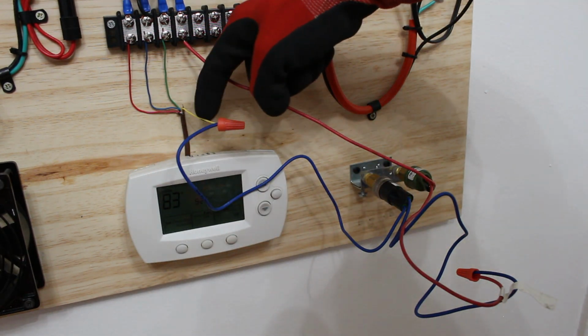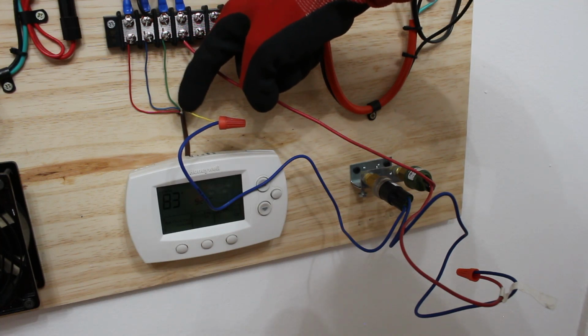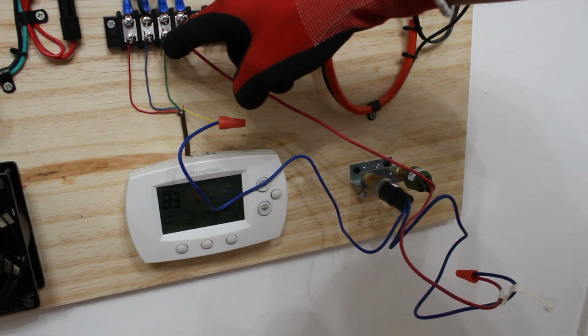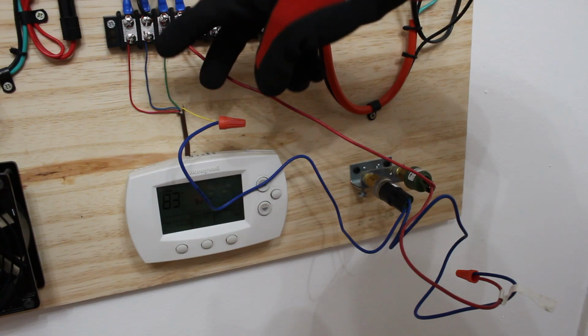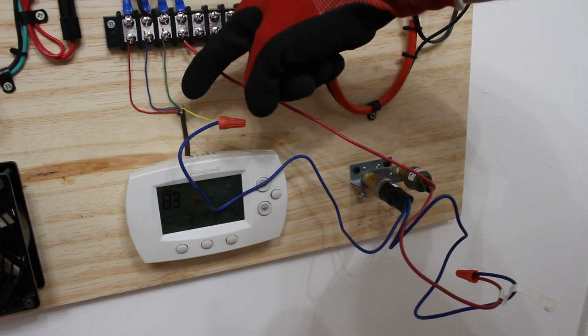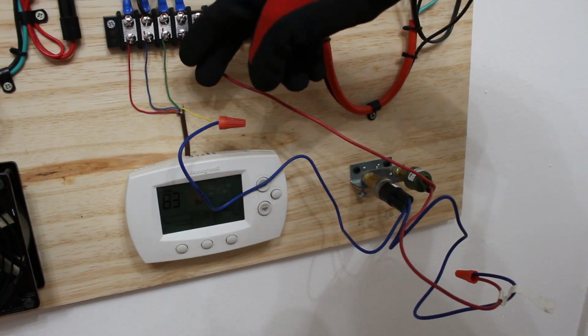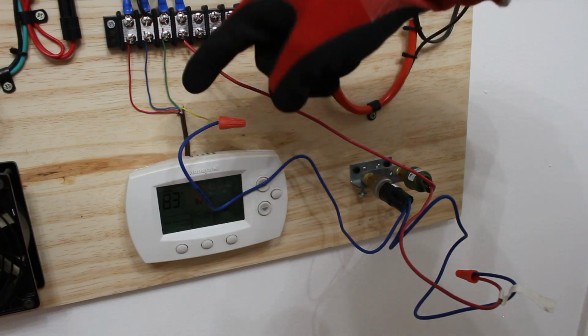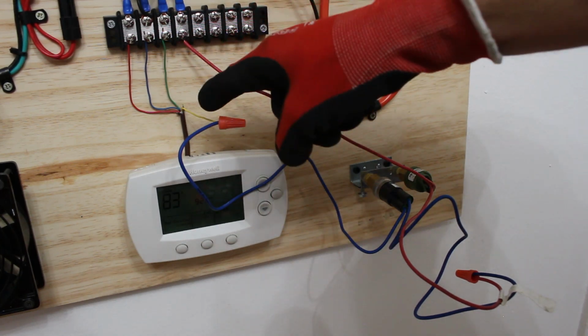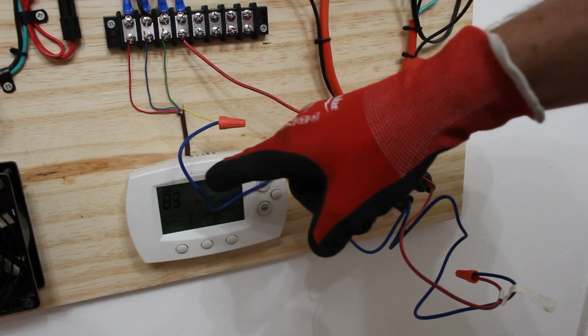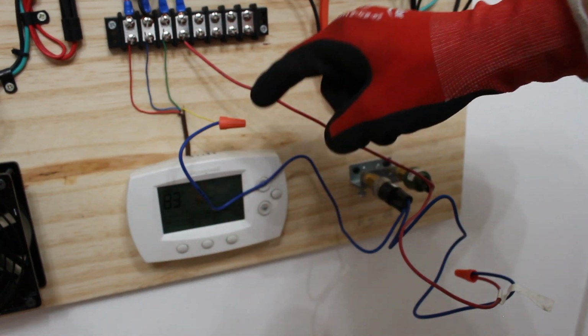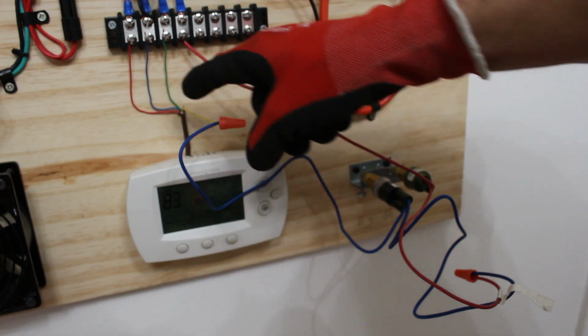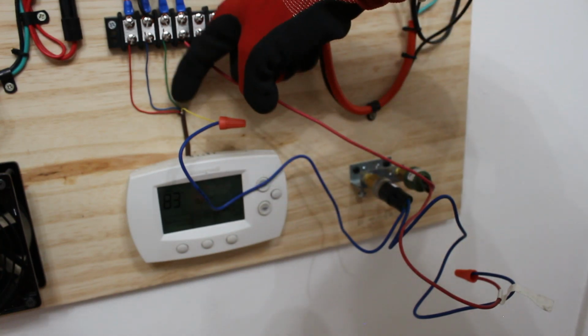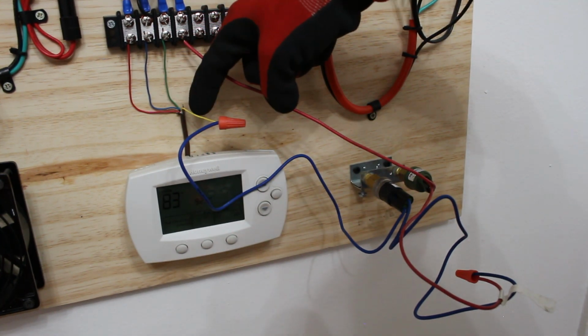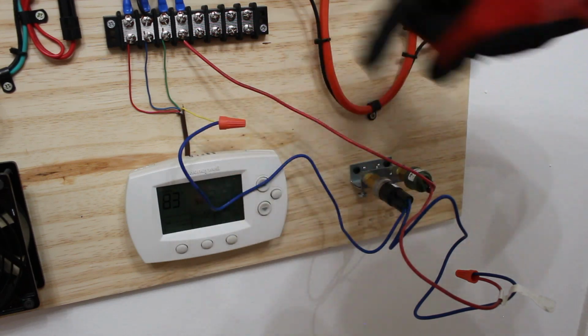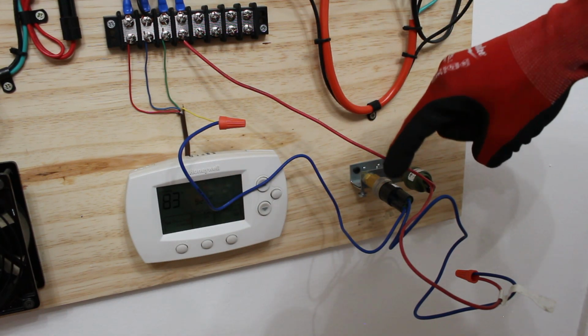So, our yellow wire right here, it's coming from our thermostat. This is our Y. We're gonna disconnect that from our circuit. So basically just cut that wire. In this case, I just unscrewed it, but you're gonna cut that wire. So the one directly from the thermostat, you're gonna take that and then take one lead of your first pressure control. In this case, it's gonna be our low pressure control and it's gonna get connected. So out of the thermostat, Y, first wire gets connected into our pressure control.